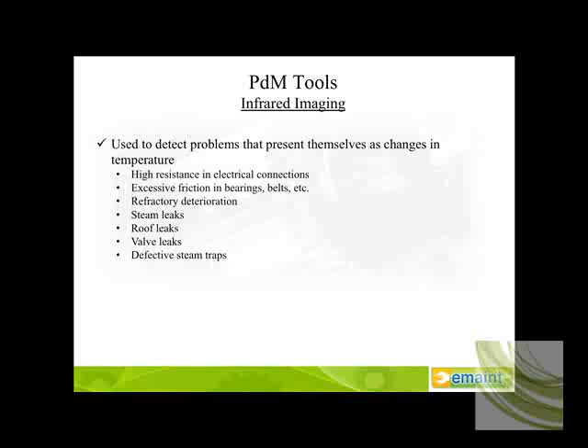So there are calculations that can be entered into the camera, calculations that can be entered into software. The point is not to go into a discussion of emissivity, but to be aware that there are external influences of a physics nature that need to be taken into account when using these types of instruments. They can also be sensitive to focus and field of view. And the reality is that there's fairly extensive training that should be required for the use of thermal imaging cameras, especially when the interest is in absolute or accurate temperature measurement of any one given target.